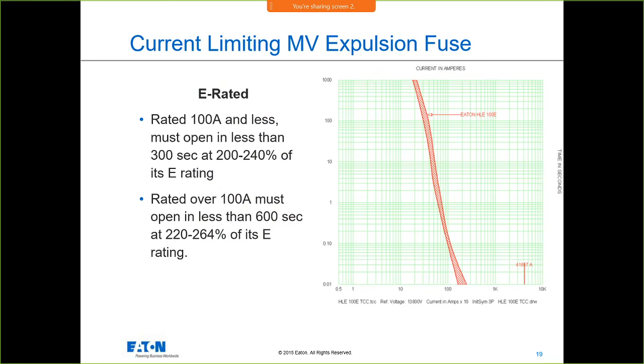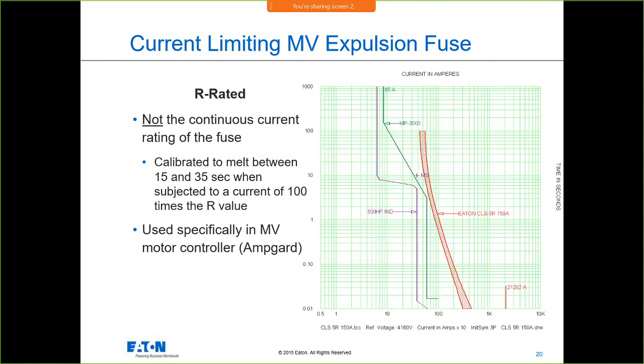Those are your E-rated fuses. They must open in less than 300 seconds at 200 to 240% of the E rating. You'll see it's a very fast-acting device, and you'll have your medium voltage motor starting. The MP3000 is a motor protection relay. A lot of those larger medium voltage motors will have relays associated with them.